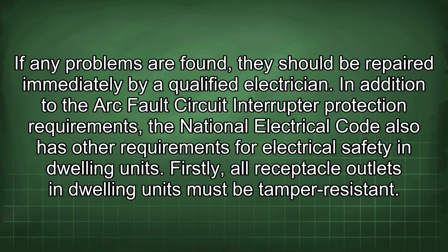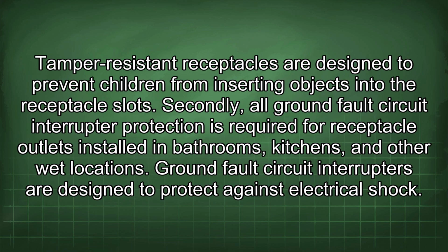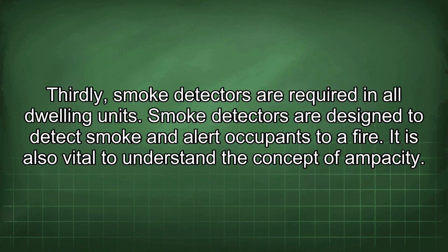In addition to the arc fault circuit interrupter protection requirements, the National Electrical Code also has other requirements for electrical safety in dwelling units. Firstly, all receptacle outlets in dwelling units must be tamper-resistant. Tamper-resistant receptacles are designed to prevent children from inserting objects into the receptacle slots. Secondly, ground fault circuit interrupter protection is required for receptacle outlets installed in bathrooms, kitchens, and other wet locations. Ground fault circuit interrupters are designed to protect against electrical shock. Thirdly, smoke detectors are required in all dwelling units. Smoke detectors are designed to detect smoke and alert occupants to a fire.